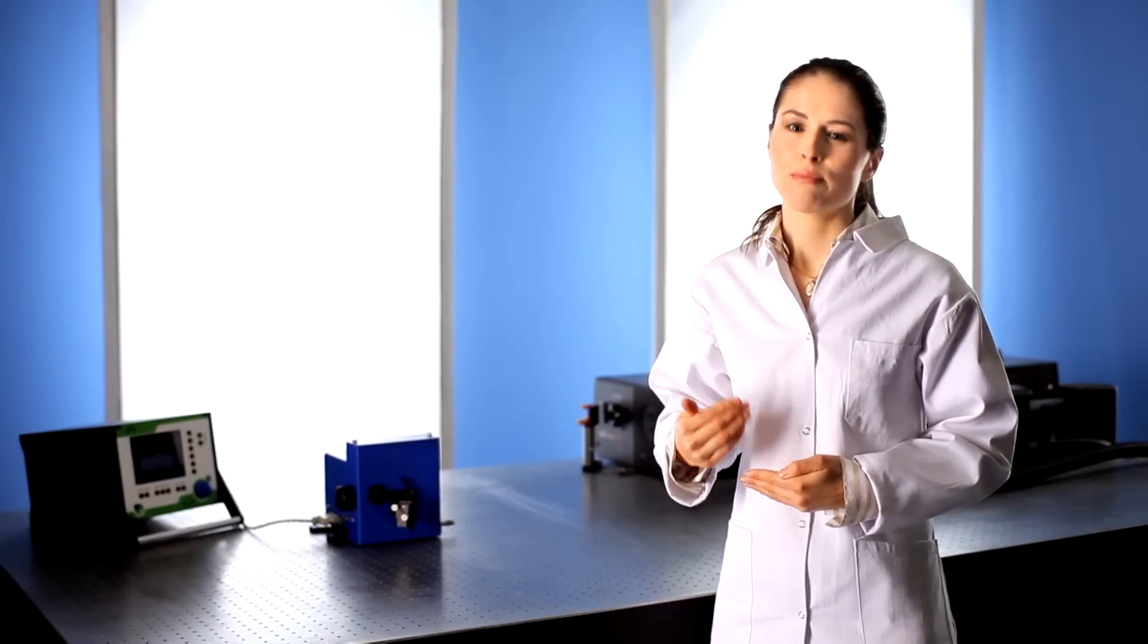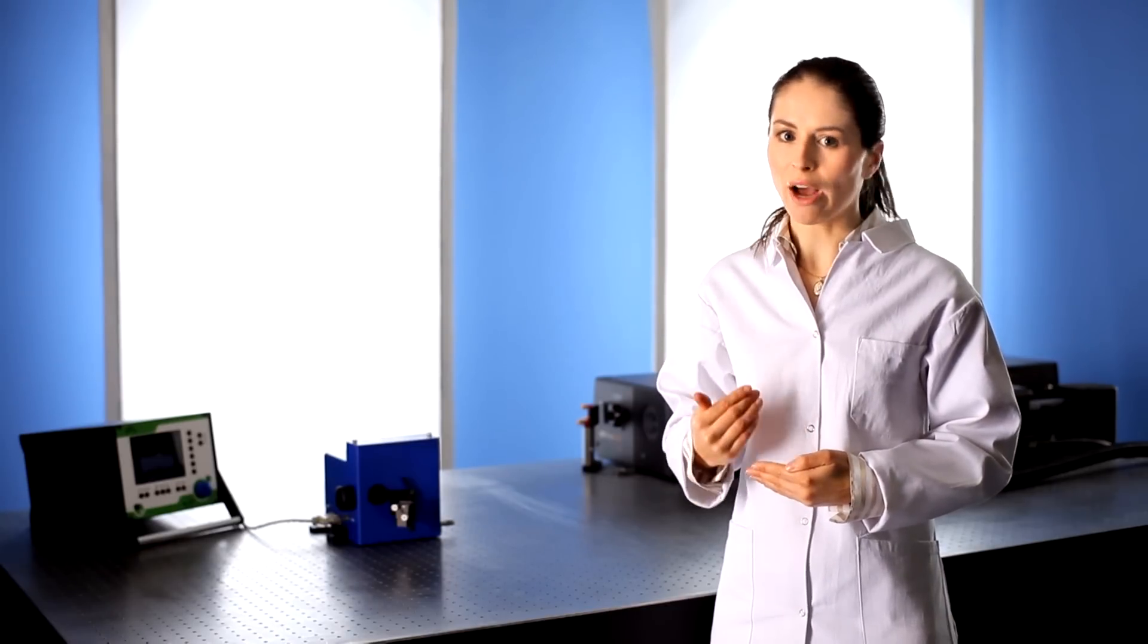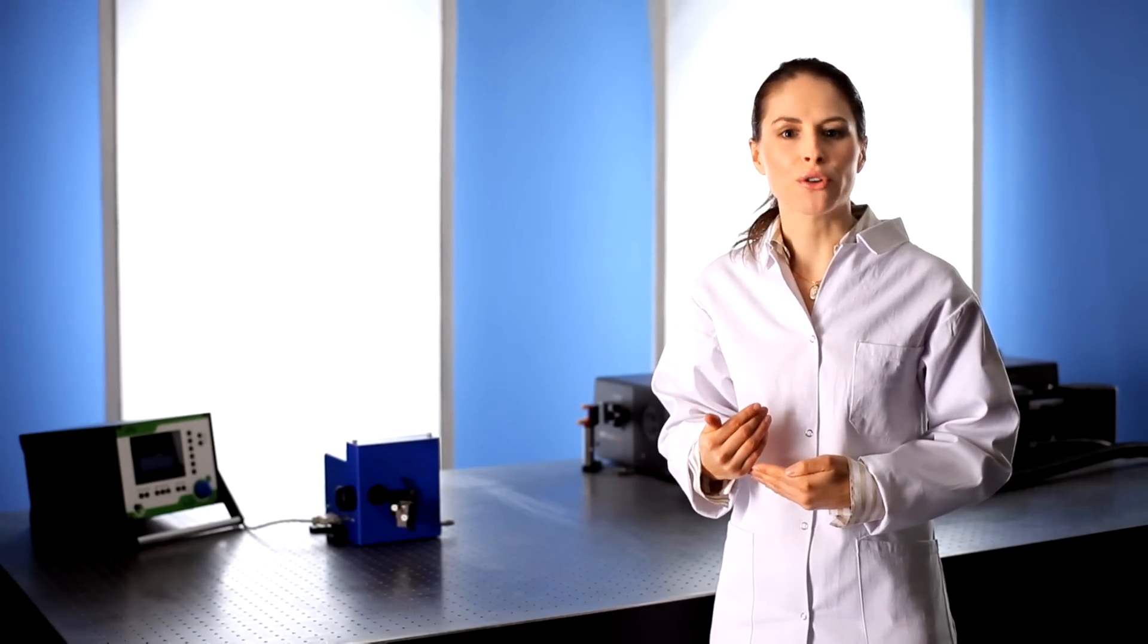When you set up pulse check, you needed to align the incoming beam. That required us to set pulse check to collinear mode. But to optimize your measurements, we now have to set pulse check to non-collinear mode. Let me show you the difference.